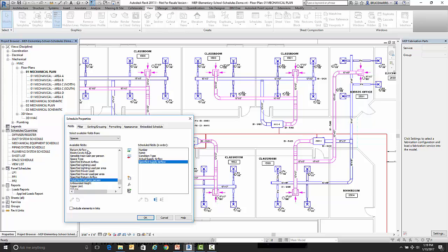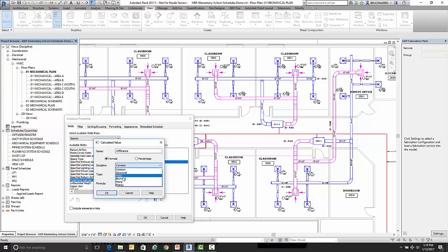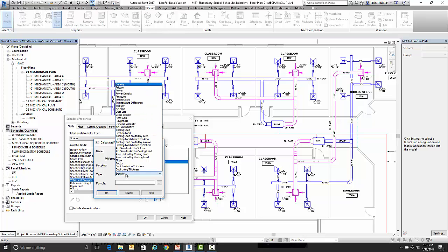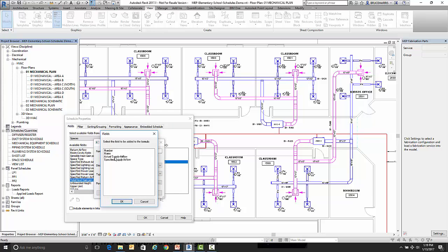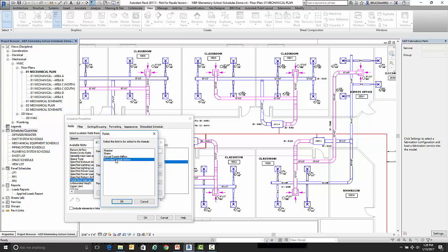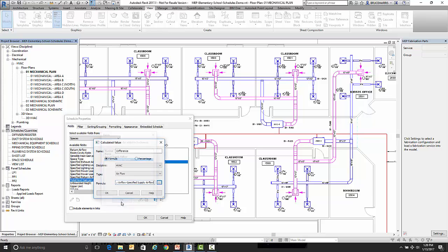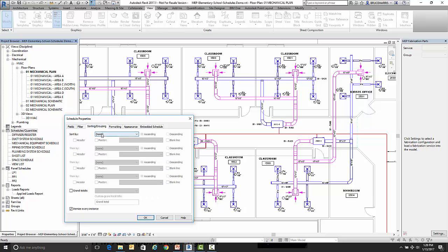Now those are the pieces of data that I need out of this space but I also want to create one calculated field. So I'm going to click on add a calculated parameter and I'm going to call this one difference. Now it's based on an HVAC value and that value is airflow and the formula I want to be is actual airflow minus specified airflow. And go OK and let's sort it by number and then one more OK.